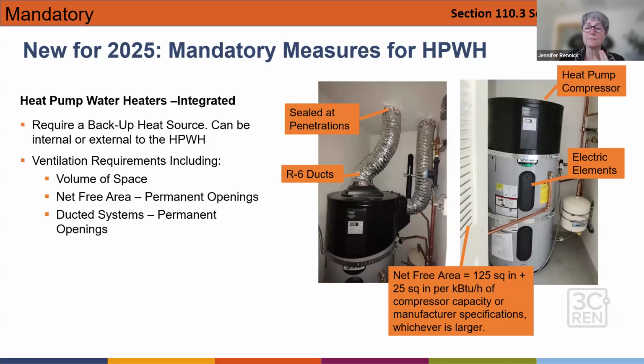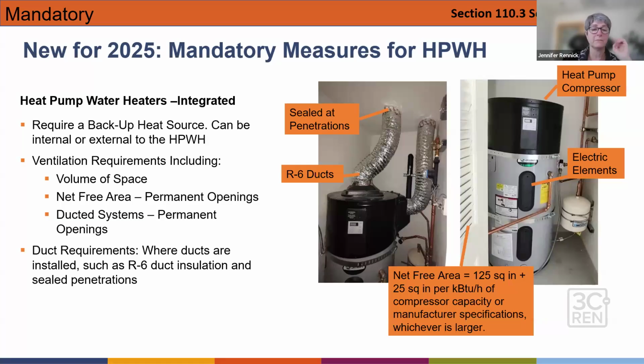So you can look at the closets, maybe not going to meet the volume of space you need, but that closet can communicate to the rest of the, say, kitchen, laundry, living area, and you would calculate the net free area of that door and meet the requirements of either a formula based on compressor capacity or the manufacturer specifications, whichever's greater. And in many instances where I've looked at that, the manufacturer's requirement has been greater. And so that, I would say, just go with that most of the time.